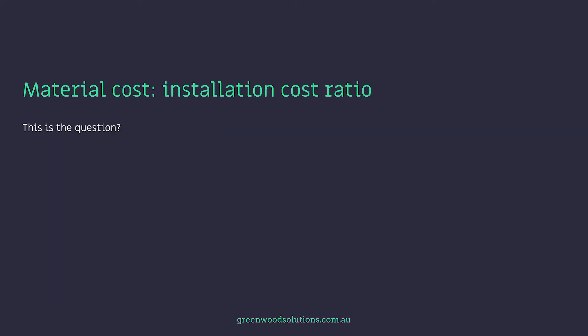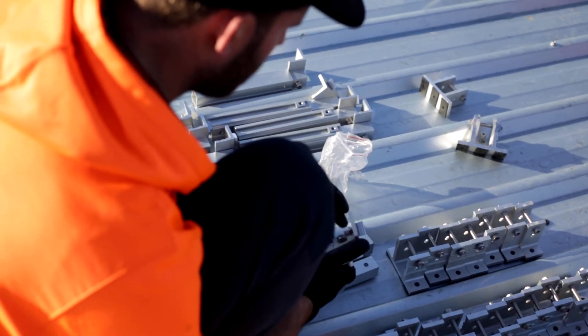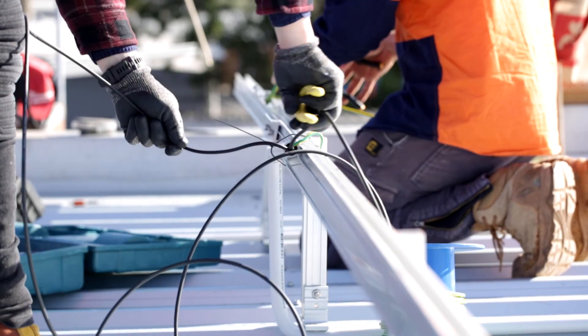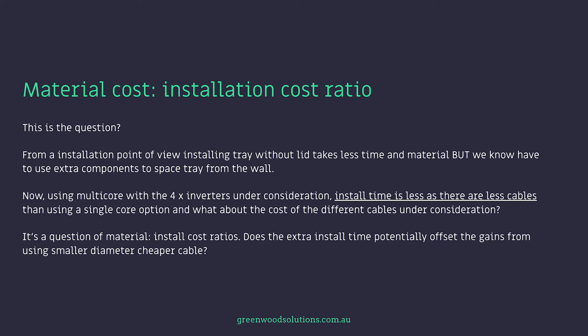Material cost versus installation cost ratio — this is the question. From an installation point of view, installing cable tray without lid takes less time and material, but we know we have to use extra components to space the tray from the wall. Now using multi-core with the 4 inverters under consideration, install time is less as there are fewer cables than using a single core option. And what about the cost of the different cables under consideration? Does the extra install time potentially offset the gains from using smaller diameter, cheaper cable? Also, if using aluminium, there are specific cable lug requirements to consider.